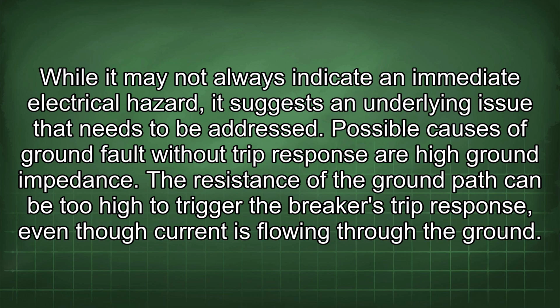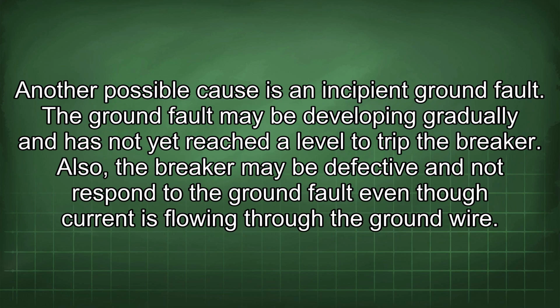be addressed. Possible causes of ground fault without trip response are high ground impedance. The resistance of the ground path can be too high to trigger the breaker's trip response, even though current is flowing through the ground. Another possible cause is an incipient ground fault. The ground fault may be developing gradually and has not yet reached a level to trip the breaker.